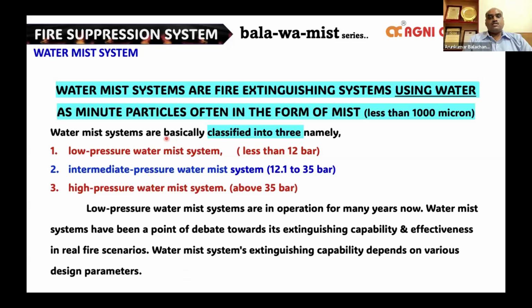In water mist, these systems are basically classified into 3 based on their operating pressures. Low pressure water mist systems operate at less than 12 bar. Intermediate pressure is from 12.1 to 35 bar, and high pressure water mist systems are above 35 bar. Low pressure water mist systems have been in operation for many years now, and water mist systems have always been a point of debate towards their extinguishing capability and effectiveness in a real fire scenario.